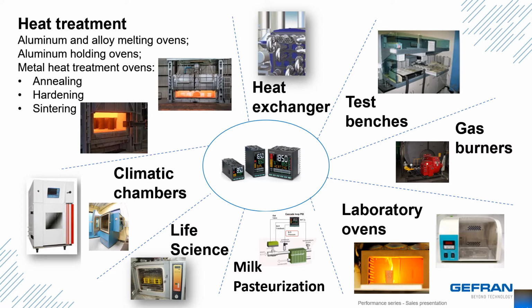Climatic chambers, also called environmental chambers, is an enclosure used to test the effects of specified environmental conditions on biological items, industrial products, materials, electronic devices, and components. It is common for a chamber to use temperature and also humidity or pressure. The Performance series can manage these as a 2 PID loop and set point programmer. Milk pasteurization. Both single loop and cascade PID loop controls can be used in the application. Cascade can compensate for steam pressure deviation before affecting the milk temperature.